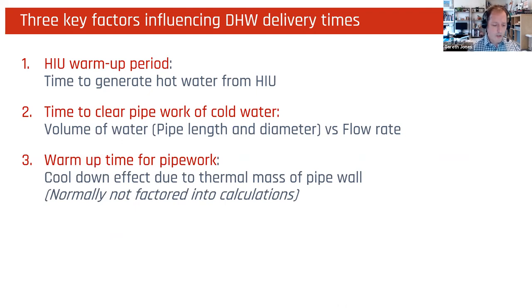If we look at the factors influencing domestic hot water delivery times, really there are three issues. One is the HIU warm-up period, the time to generate hot water from the HIU. The BSRIA HIU tests will actually show how long that takes. There's then the time to clear the pipework of the cold water. So you look at the volume of water, so pipe length and diameter versus flow rate. And those are the two things that we normally see being calculated.